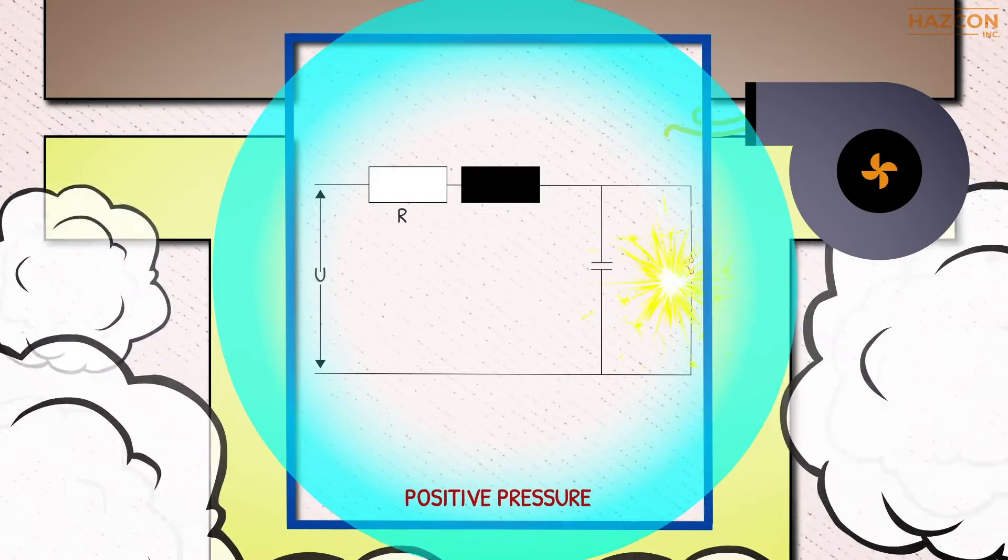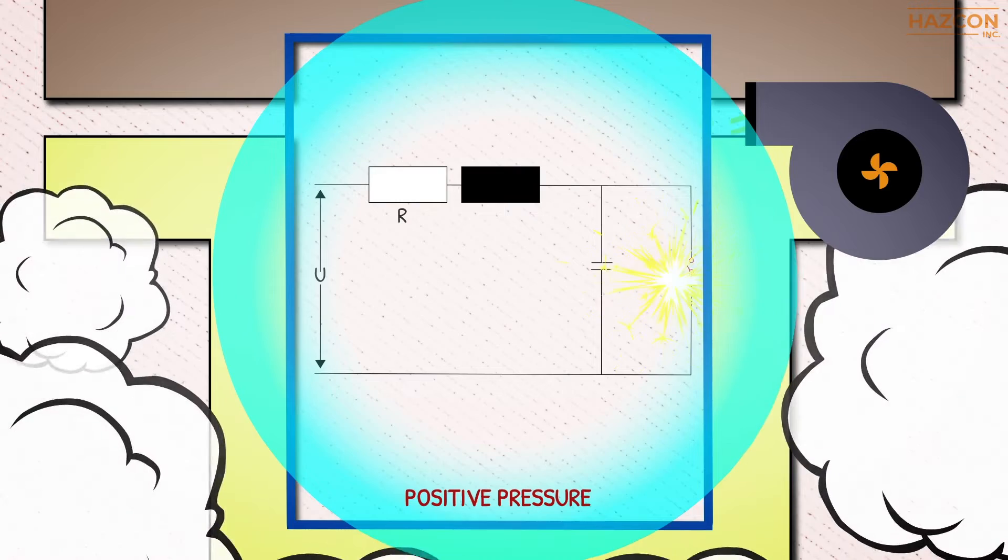The purging and pressurization technique creates a safe area inside the enclosure, meaning that uncertified equipment can safely be installed within it, even given a hazardous environment outside the enclosure.